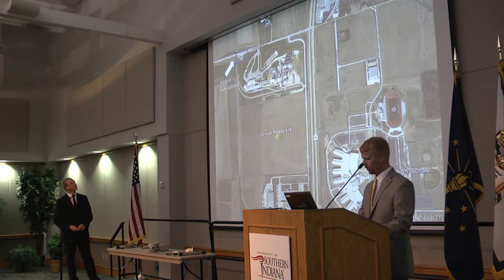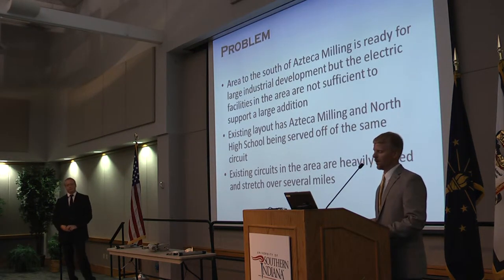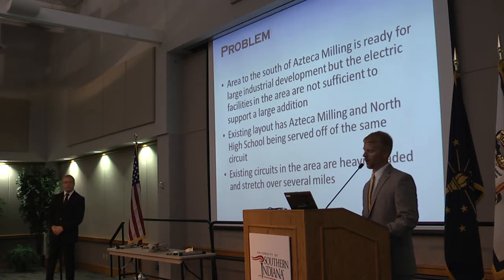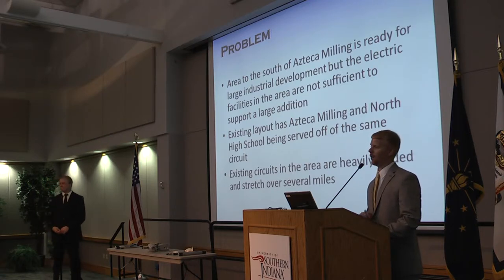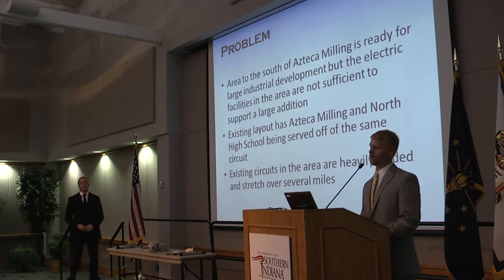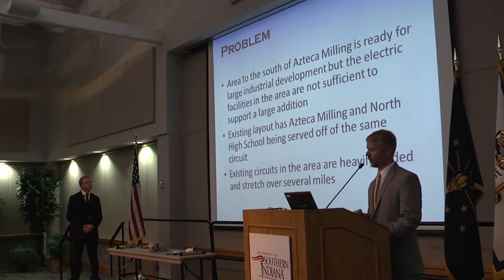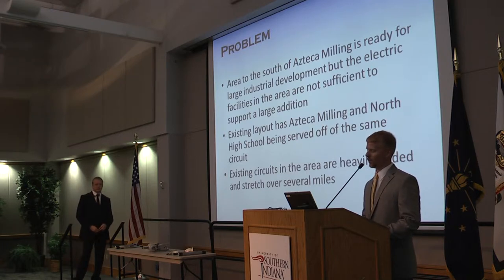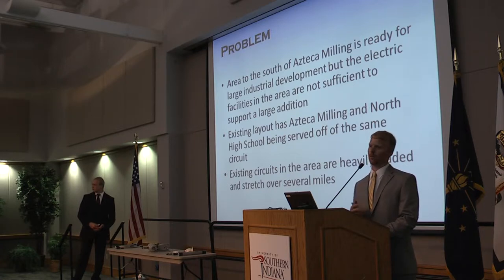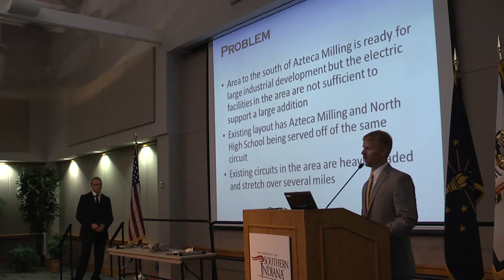So the problem that we were given is that the area south of Azteca Milling is ready for large industrial developments, but the electric facilities in the area are not sufficient. Basically, in the area we have two circuits existing, and they do not have the capacity to pick up another large load. The next problem is that the existing layout has Azteca Milling and North High School being served off the same circuit. The problem with this is that Azteca Milling is a key customer with Vectren. So in order to give them the most reliable power, we try and keep them on a dedicated circuit. So we're going to try and address that issue.